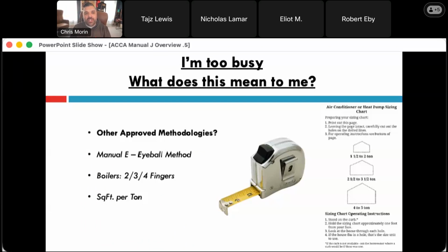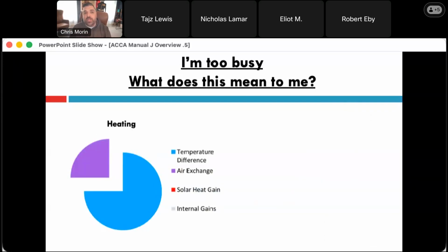And what's just as funny to somebody that knows how to do system design is square feet per ton. Yet that is probably the most obvious way that contractors try to size systems. It's unfortunate because it leads to typically oversized units that have trouble keeping up. And here in Austin, you have a lot of moisture problems. So an oversized system that short cycles is never going to remove all those latent gains. So it's really important that we focus on sizing, particularly around the cooling side.